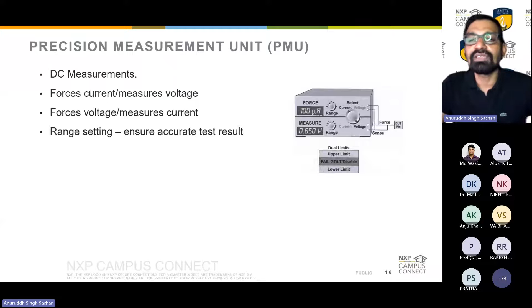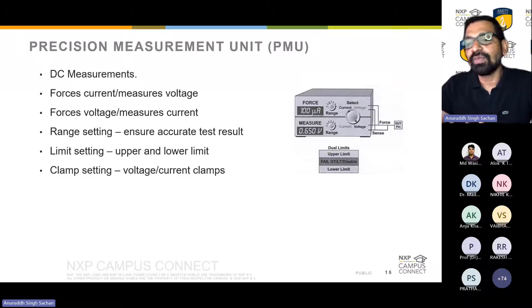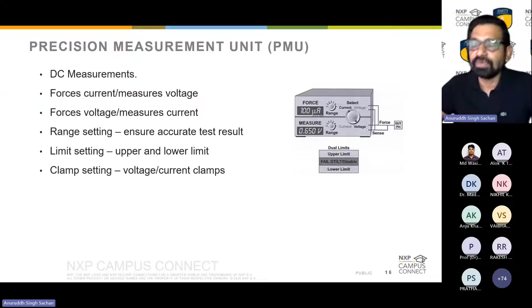Limit setting lets you set upper and lower limits. Clamp setting lets you set a clamp for voltage and current so you don't accidentally burn the part. For example, you can set a 2 milliampere current clamp, and it will not go beyond that. Similarly, if 1 volt is the voltage clamp, even if the chip tries to output more, it will not go beyond that. So you can set your limits based on range or accuracy. All these functions the PMU can handle, and that's inside the ATE.